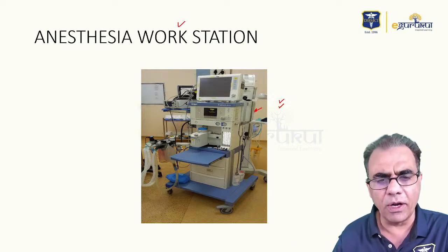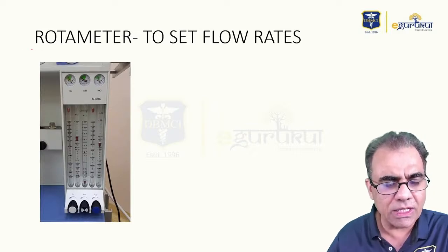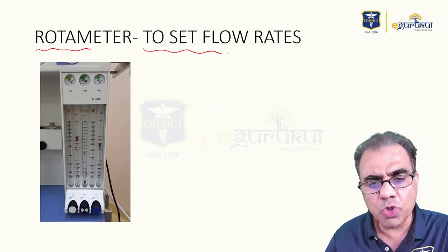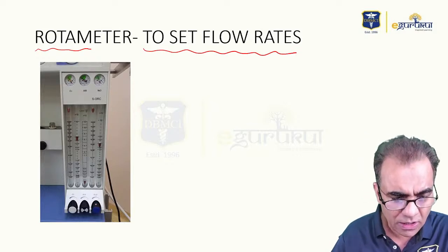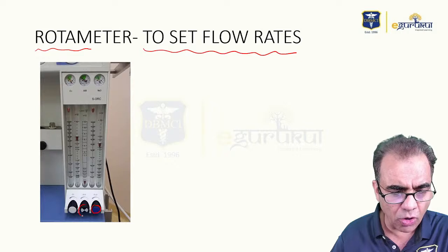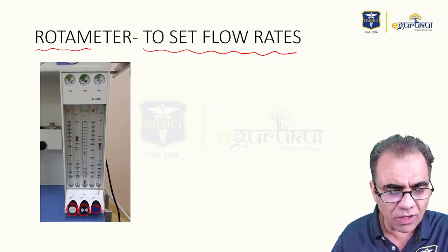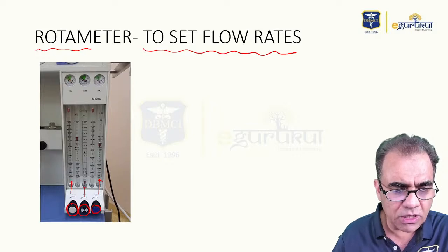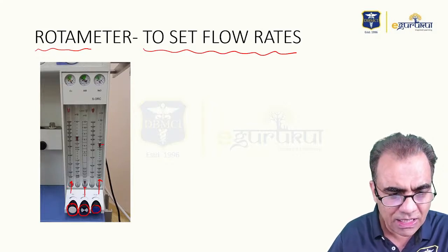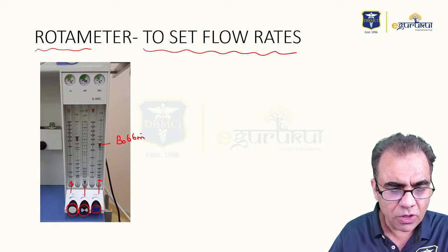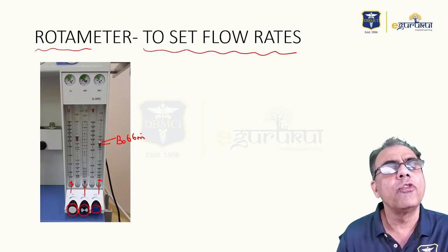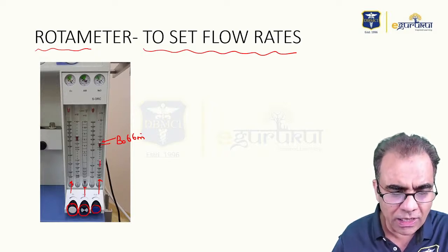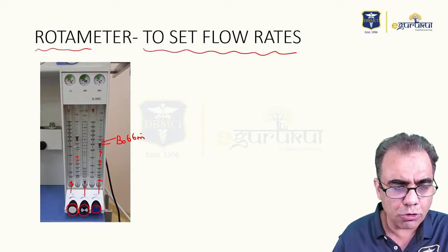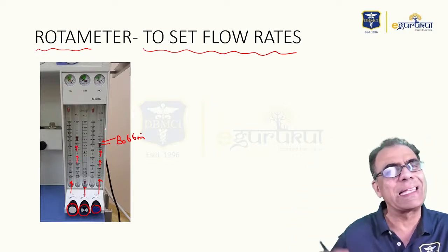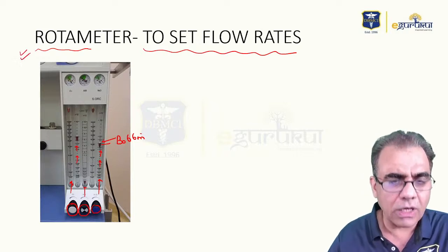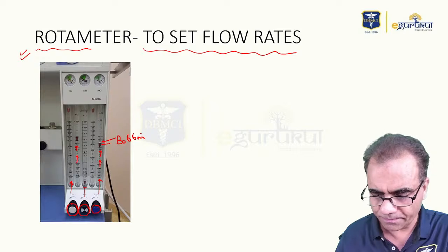Another important component of the anesthesia machine is the rotameter. The rotameter is used to set the flow rates. So this is a rotameter, which has knobs. By rotating these knobs clockwise or anti-clockwise, you can increase or decrease the flow of each gas into this flow meter tube. And this structure is called the bobbin. It is the upper level of the bobbin which determines the flow rates. So by rotating this knob, you can increase or decrease the flow of gases through these flow meter tubes, and based on that you can set the flow rates. So simply, the rotameter is used to set the flow rates.